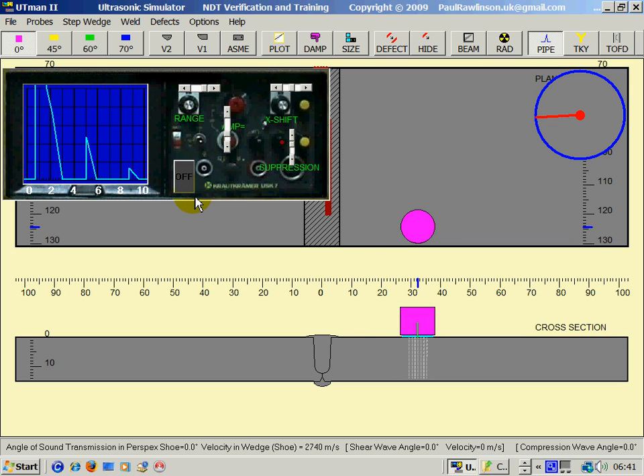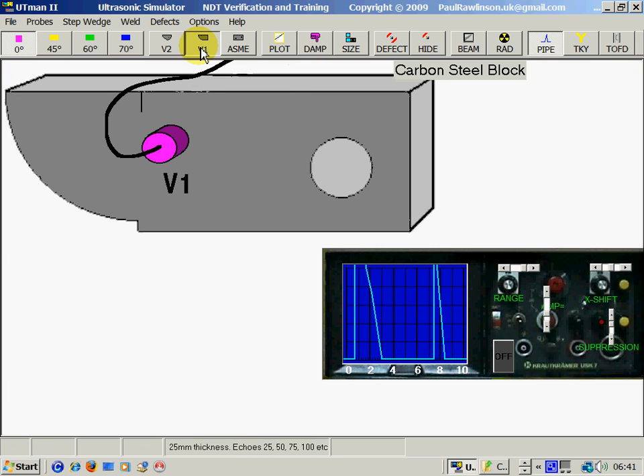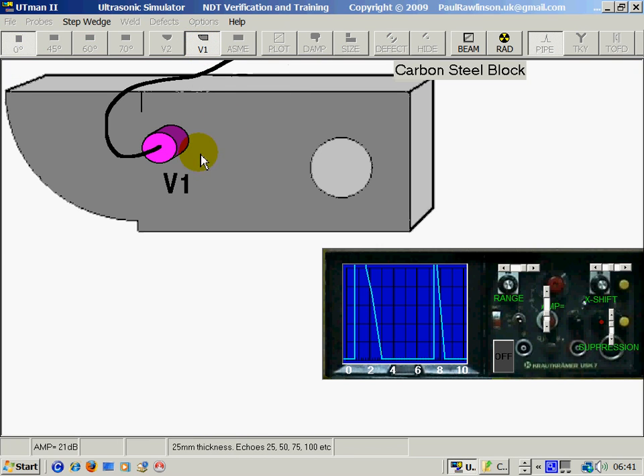Now to calibrate for zero we can click on the V1 block here. The V1 block is 25mm thick.